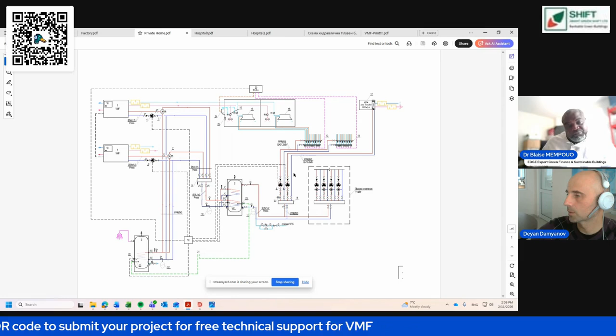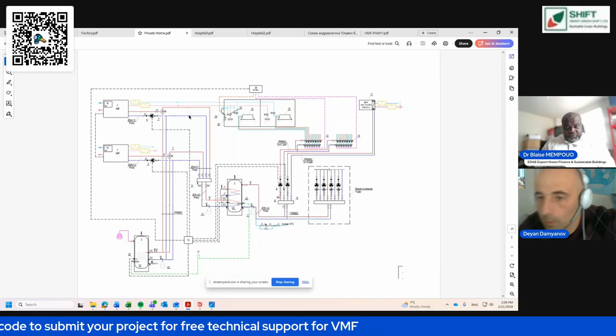Very interesting for this project is that we integrate an underfloor heating system to the VRF system. So the whole project is covered with underfloor heating. If I remember correctly, for this project we have more than 9,000 meters of pipes for underfloor heating. So that water part is integrated into our system. This shows how flexible VRF is with external systems and how we can integrate them. Basically, in winter time the underfloor heating is working and the chilled beams are switched off, but the ventilation continues to work.